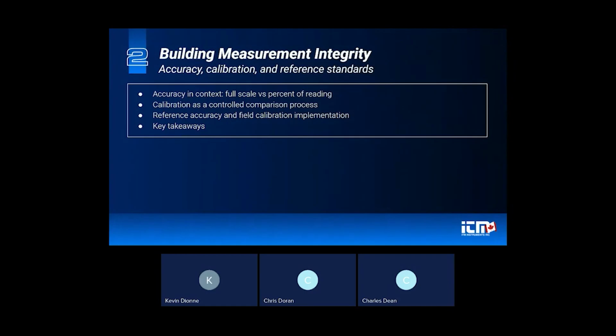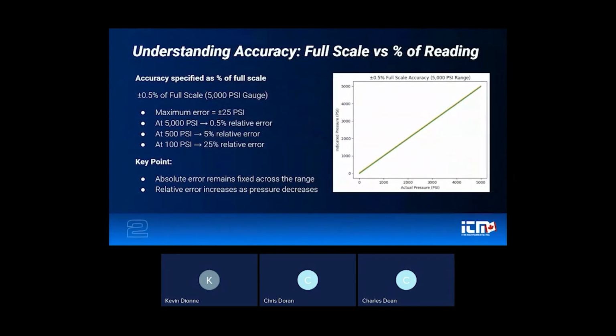So in pressure measurement, accuracy, calibration, and reference standards are often discussed together, but they serve very distinct and specific roles. So I'm going to walk through each of these concepts individually, and I'm going to show how they're supported by different crystal engineering instruments, not from a product standpoint, but from a measurement function standpoint. The goal here is to clarify where each tool fits in the measurement chain before we move on. So when we talk about understanding accuracy, it's important to look beyond a single specification on a data sheet and understand how that accuracy behaves across the operating range of an instrument.